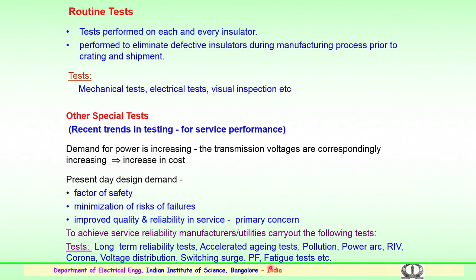So, we will discuss the importance of some of the testing here. First, thermal mechanical performance. This test is mainly performed to ensure there is no movement of hardware, particularly the cap and pin for the insulator. There should not be any movement, as the hardware is coated with a bituminous layer to prevent corrosion when in contact with the cement.